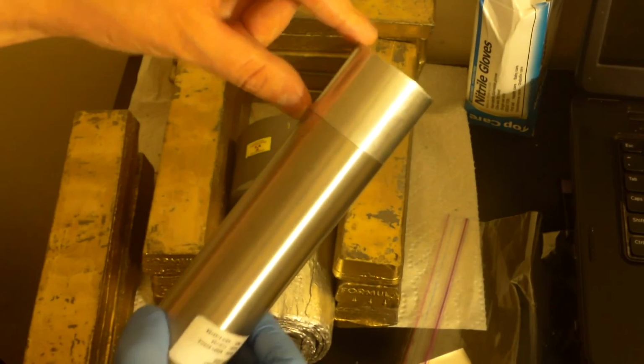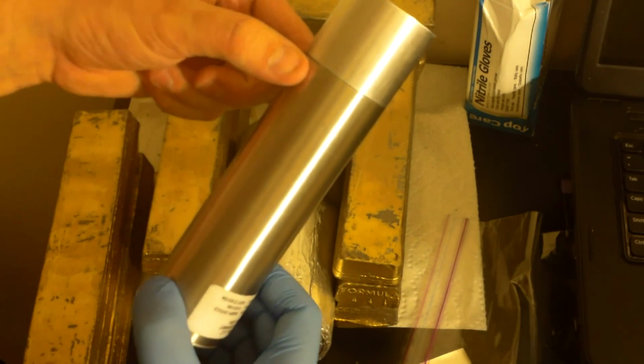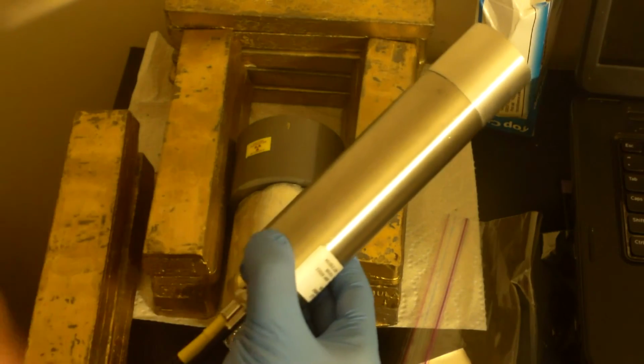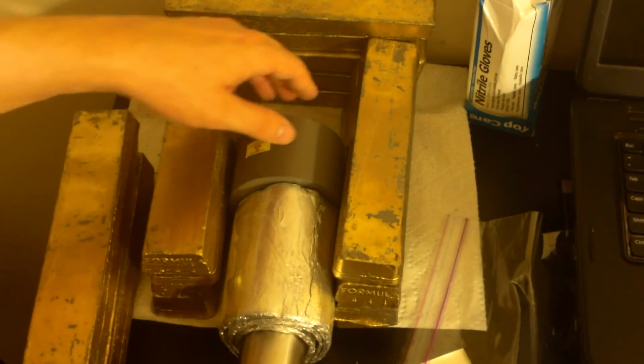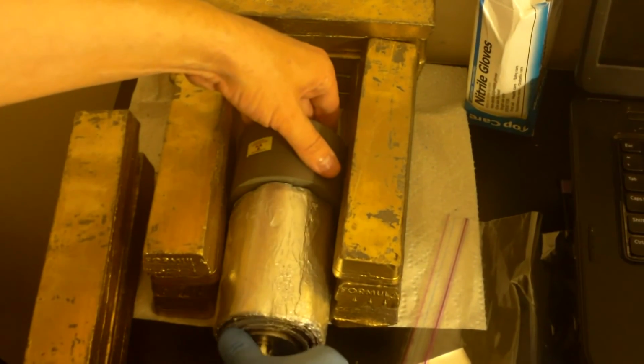This is the crystals in the front with a photomultiplier tube in the back. And this will detect the gamma rays that hit it, and the photomultiplier tube will amplify them and send them out as little pulses of current. So let's stick that back in. This, by the way, is rolled up lead sheeting.